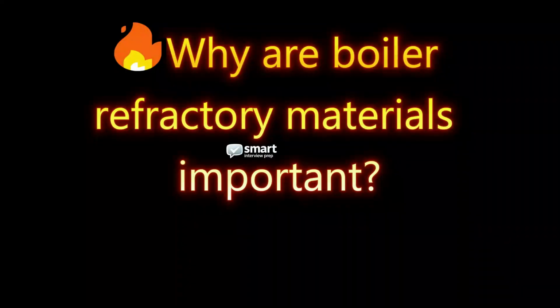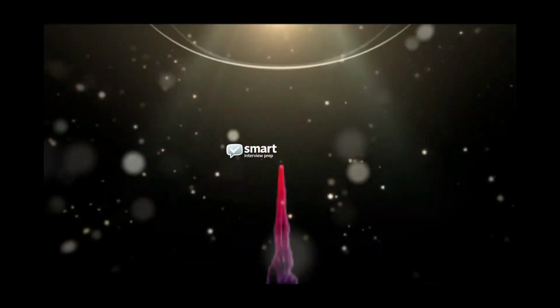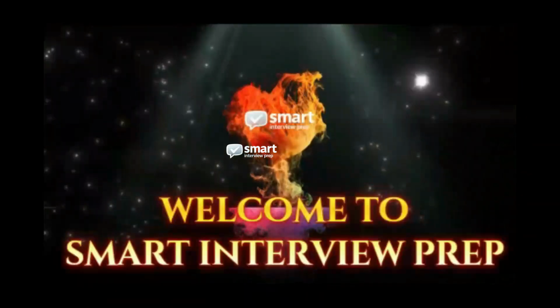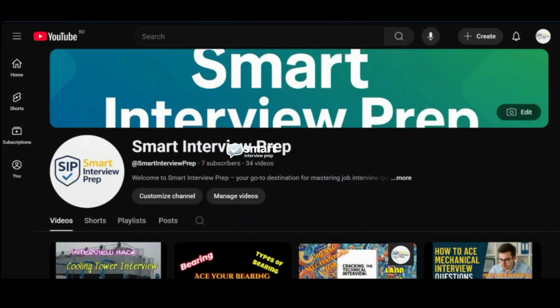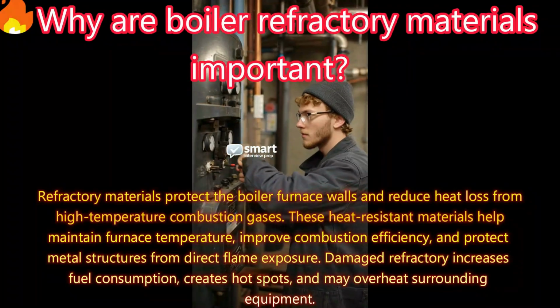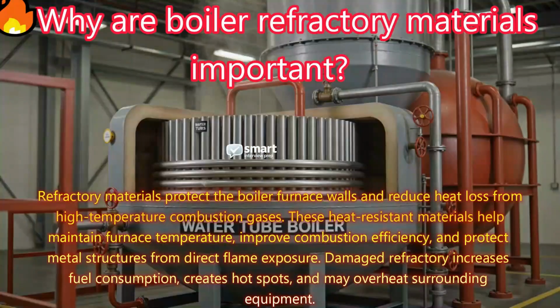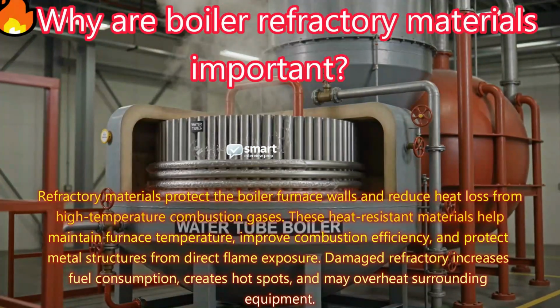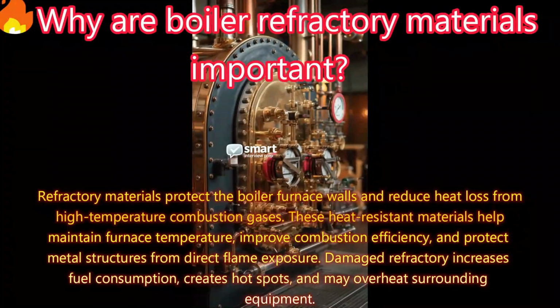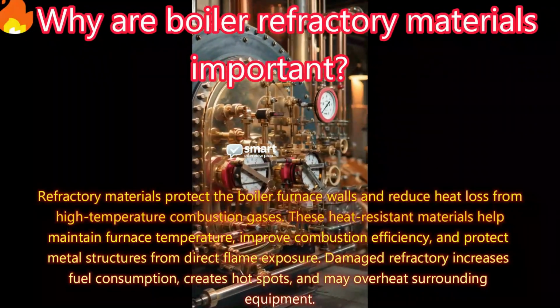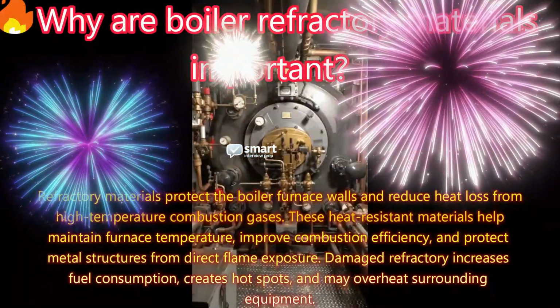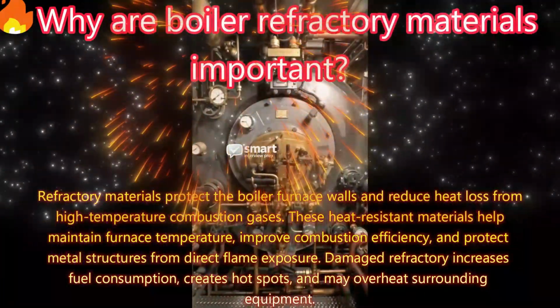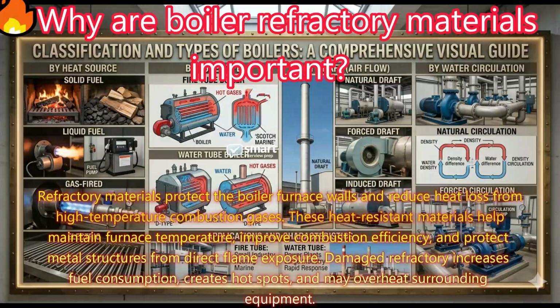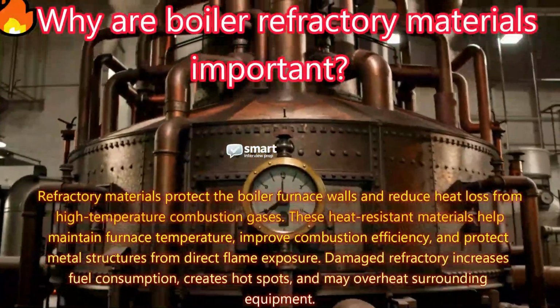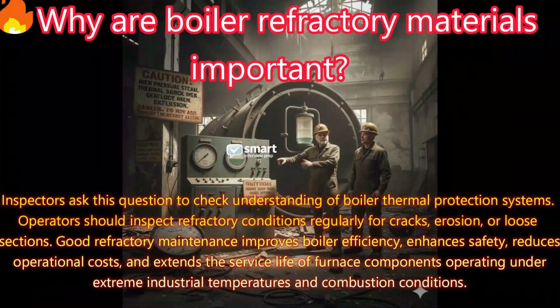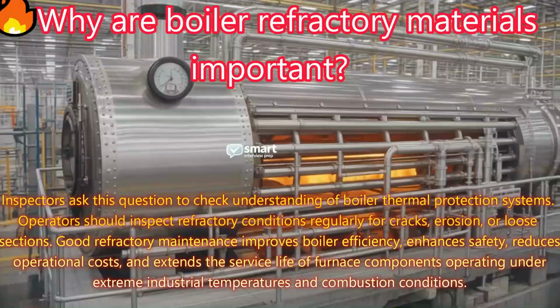Why are boiler refractory materials important? Answer. Refractory materials protect the boiler furnace walls and reduce heat loss from high-temperature combustion gases. These heat-resistant materials help maintain furnace temperature, improve combustion efficiency, and protect metal structures from direct flame exposure. Damaged refractory increases fuel consumption, creates hotspots, and may overheat surrounding equipment. Inspectors ask this question to check understanding of boiler thermal protection systems.